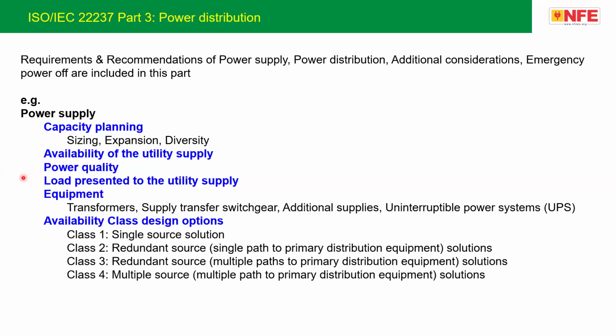And now, as Mr. George explained, the availability class of the design option. We have four classes, similar to tier 1, tier 2, tier 3, and tier 4. Class 1 is where we feed a single path to the primary distribution equipment with a single source. In that, a single fault in a functional element can result in loss of functional capability. In class 2, there is a single path to the primary distribution equipment with a redundant source. In that case, a single fault in the source shall not result in loss of functional capability of the path, and routine plant maintenance of the source shall not require the load to be shut down.